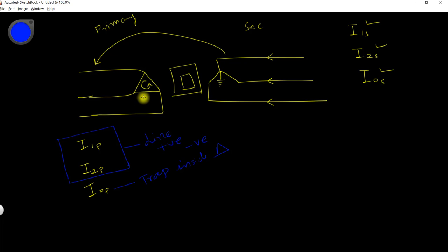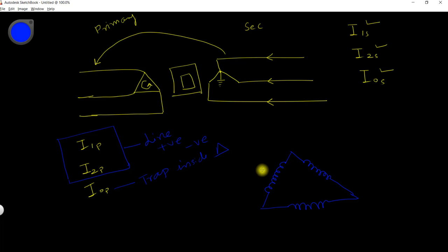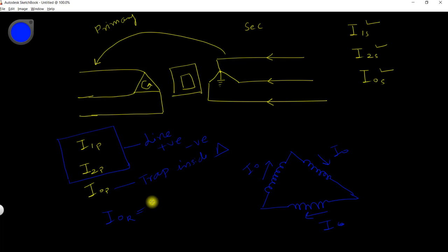Let's prove that the zero sequence component is trapped inside the delta. We draw the delta winding and the zero sequence currents I₀ for each phase. We know that for zero sequence components: I₀_red = I₀_yellow = I₀_blue — all are the same in magnitude and the same in angle.